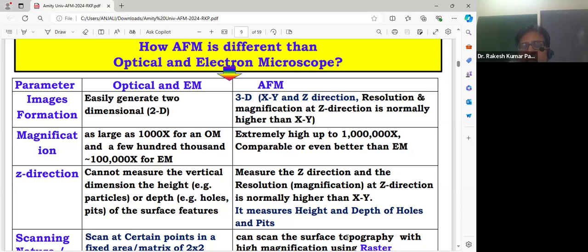One very important point is that in AFM, the resolution in the Z direction is better than in the XY direction. This helps us to easily detect the depth, that is the tops and hills, the tops and valleys at the surface level, or the height of any particle. If there are any pits, the depth of the pits can be easily identified, because it provides us three-dimensional images.